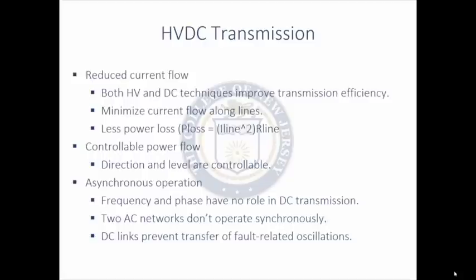The direction and level of power flow between sending and receiving end of an HVDC link is fully controllable and unaffected by most events occurring within the adjacent AC networks. And then finally, another advantage of HVDC is asynchronous operation. If you remember before, we talked about one of the limitations of current power networks or grids being the need for synchronization. Because waveform frequency and phase have no role in DC transmission, it's not required that the AC networks on either side of the HVDC link operate synchronously. DC links can prevent transfer of fault-related oscillations, and as such, in certain cases, fight against cascading outages or blackouts.